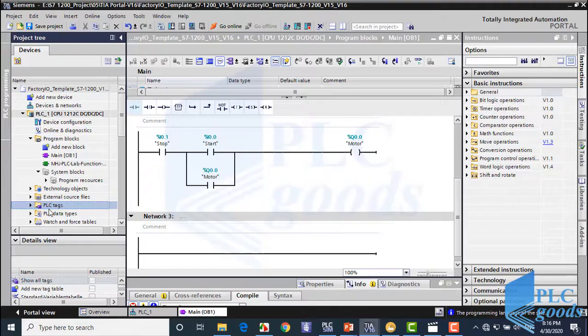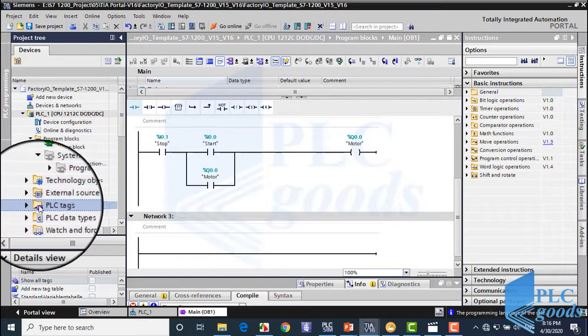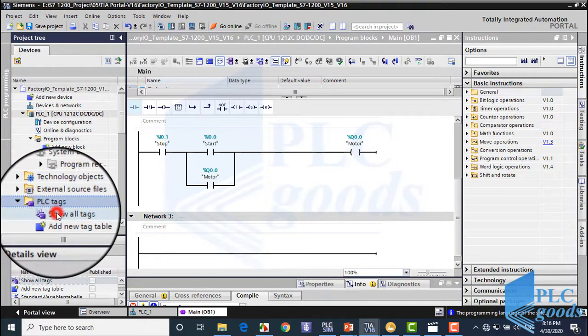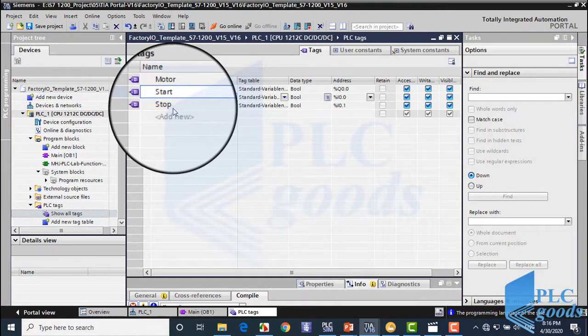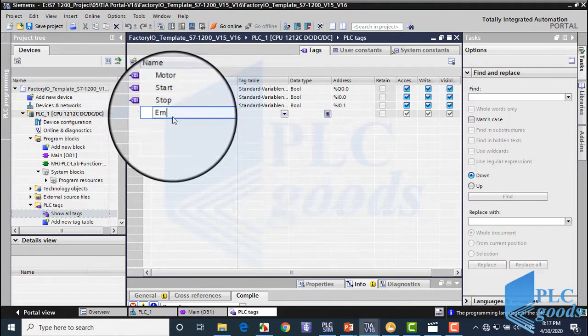Now we need to write a PLC program. Let's start with the program from the previous video. We have some sensors and actuators which must be connected to PLC inputs or outputs. First, let me define suitable tags based on our used devices in the plant. From the previous exercise, here are suitable tags for the first PLC output and I0.0 and I0.1 addresses. We have an emergency push button connected to PLC input with I0.2 address.